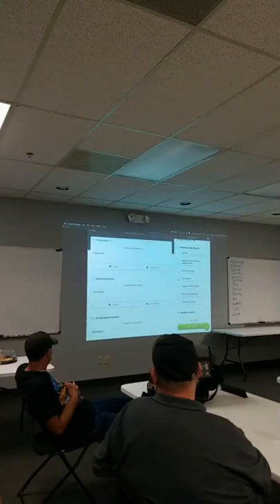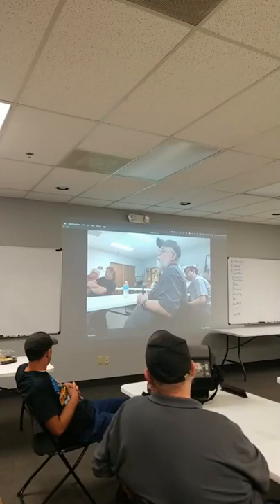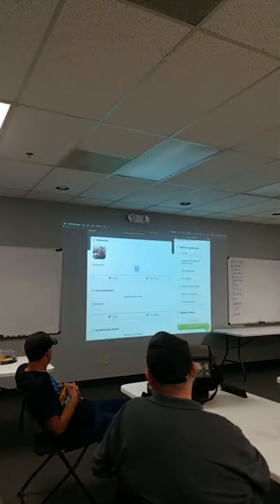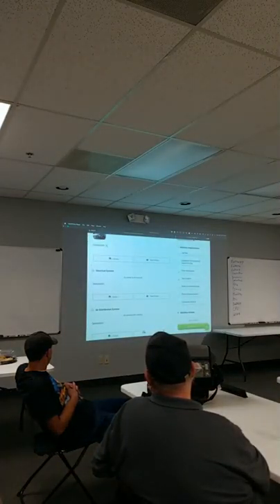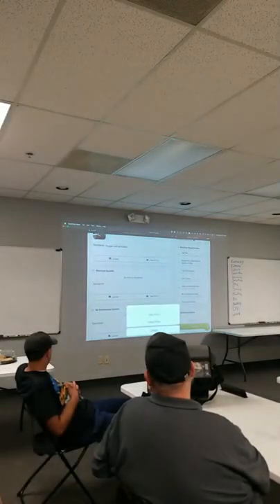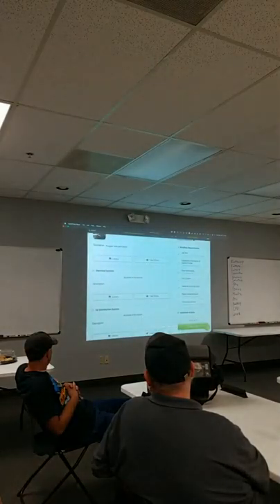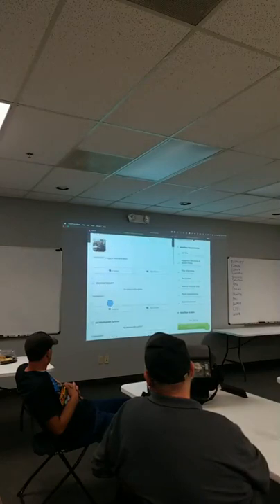Any photo documentation, this grabs information so you can take a photo of the thermostat or whatever you want to take a photo of. You hit use photo. If we want to put any notes on that, we can, you know, plugged wire penetration. And if you want to tap on that photo, you can view it, delete it, whatever you want to do, but those will also tie in. So you got your thermostat, your electrical system, your air distribution system, air filtration, condensate, anything you want to photo document. Now these can also be accessed through this hotkey down here at the bottom.